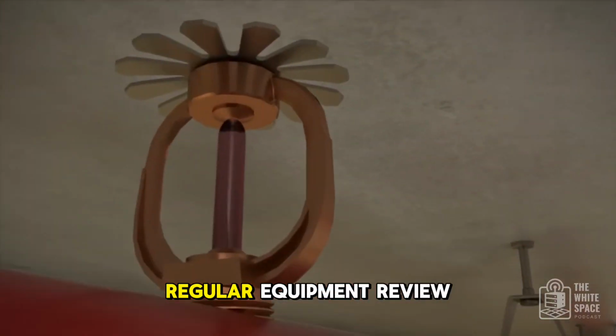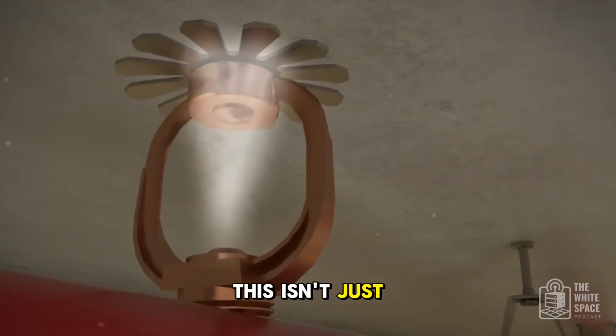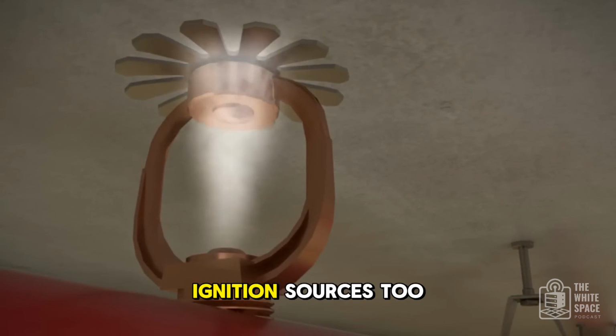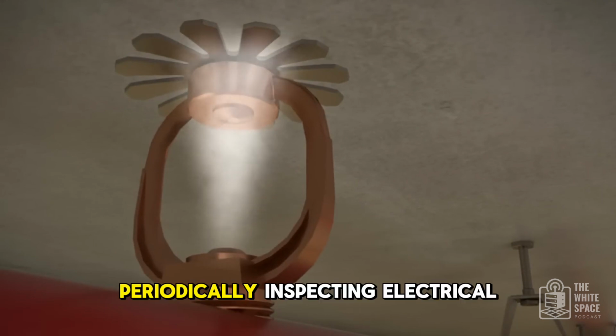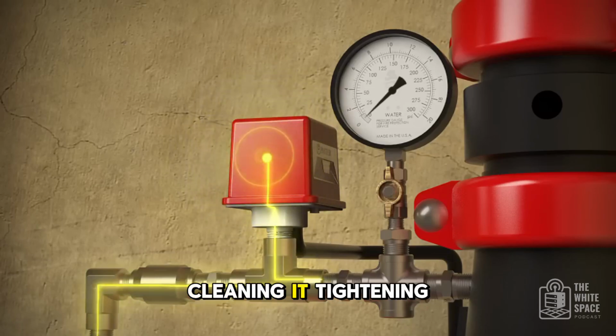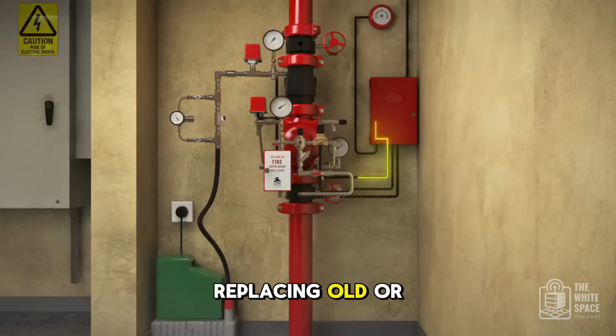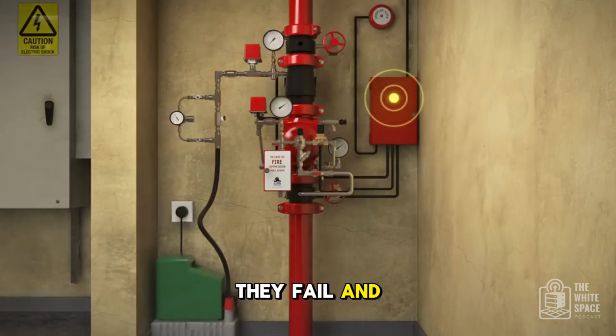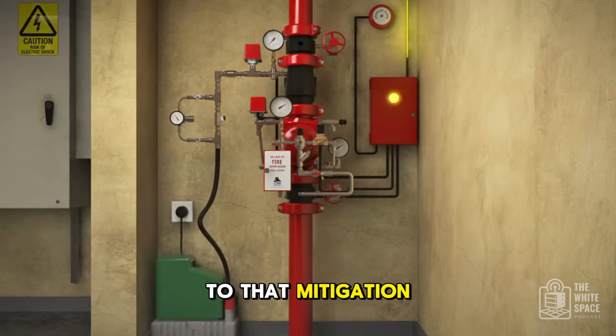First, regular equipment review. This isn't just the fire systems, but the potential ignition sources too. Periodically inspecting electrical gear, cleaning it, tightening connections, replacing old or dodgy components before they fail and cause a fire. It ties back to that mitigation step.